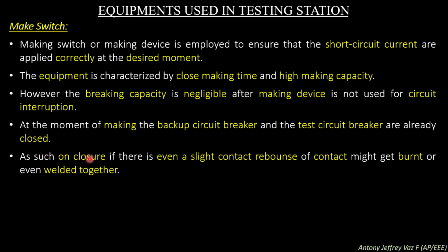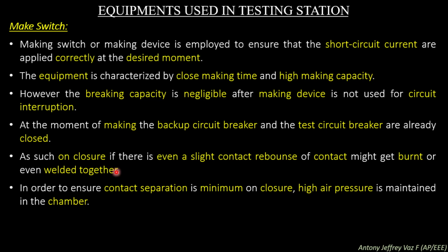As such, on closure, if there is even a slight contact rebound, the contacts might be burnt or even get welded together. So in a make switch, when the contacts rebound, this ill effect is caused by burning the metal and welding it together. So, in a make switch, contact bounce should be avoided.